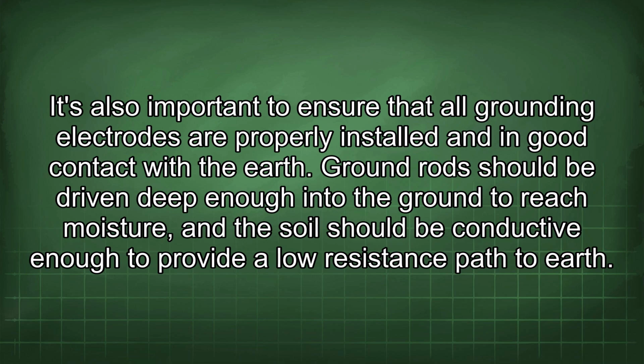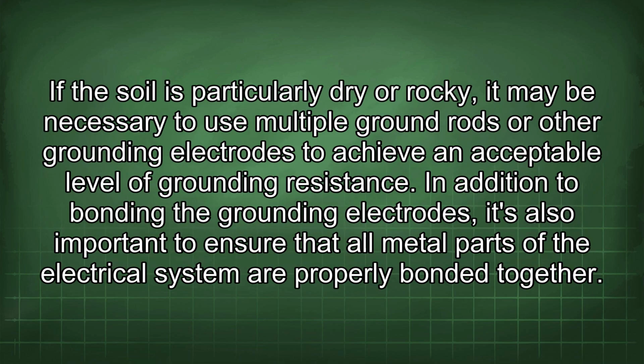Ground rods should be driven deep enough into the ground to reach moisture, and the soil should be conductive enough to provide a low resistance path to earth. If the soil is particularly dry or rocky, it may be necessary to use multiple ground rods or other grounding electrodes to achieve an acceptable level of grounding resistance.